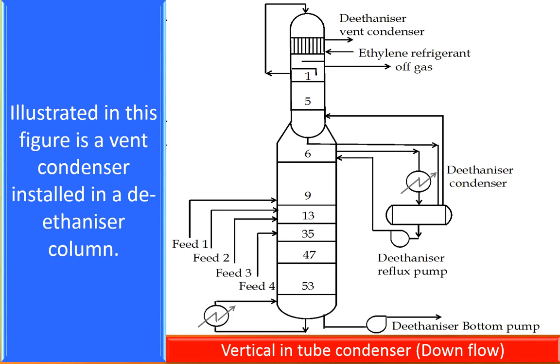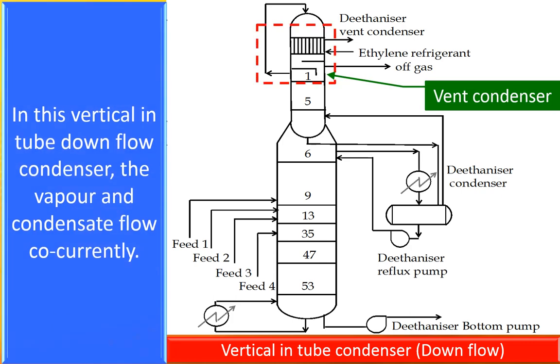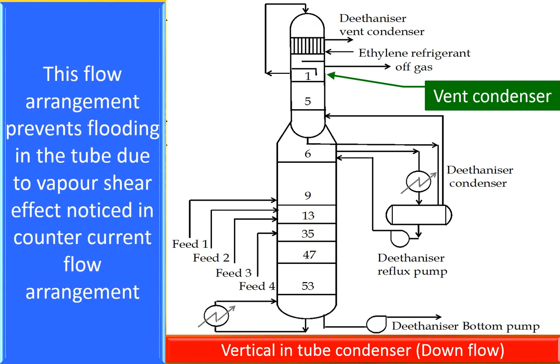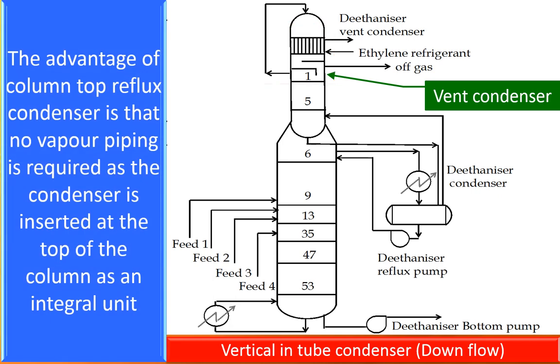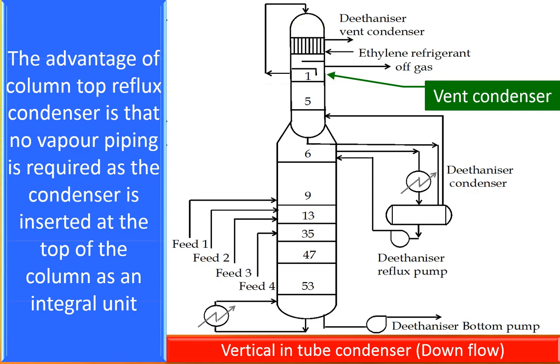A vent condenser installed in a deethanizer column is an example of a vertical in-tube condenser where vapor and condensate flow co-currently. This co-current flow arrangement prevents flooding in the tube due to the vapor shear effect noticed in counter-current flow. The advantage of a column-top reflux condenser is that no vapor piping is required, as the condenser is inserted at the top of the column as an integral unit.